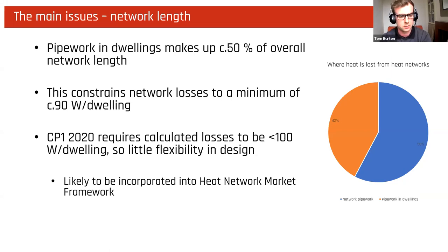The other main issue that we see with the current configuration is the overall length of the network, and more specifically the terminal run. So this is the pipe within dwellings. Whilst when you're in a flat it doesn't look like a significant amount of pipework, across the entire development, pipework in dwellings is about 50% of your overall network length. And this constrains your losses to a minimum, even if you optimize from a temperature perspective and an insulation perspective. The best you can hope for is about 90-ish watts per dwelling heat losses.